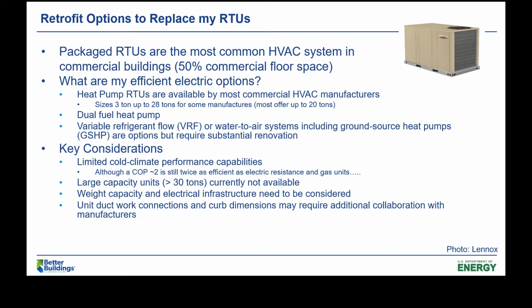Some issues that might arise are, say, the weight issue under the key considerations table. If you're trying to accommodate your entire heating load, or maybe it's oversized as Paul was alluding to on the previous slide, it may require a larger rooftop unit in a 1-for-1 replacement scenario, which may have weight considerations. For colder climates, this might be more common, at least with current technologies on the market.